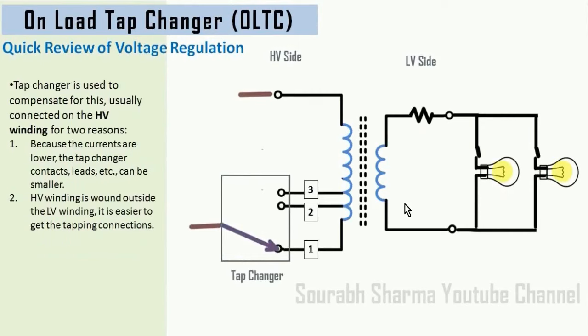This is always done at the high voltage winding because of two main reasons. Number one: the HV winding is always wound on the outer side, therefore it is easy to access. Number two: at the HV side, the winding current is comparatively low compared to the LV side, so it is easy to make and break the circuit without heavy sparking. As it is highly desirable that continuity of electrical supply must always be maintained, the tap changing process is required to be done when the transformer is on.